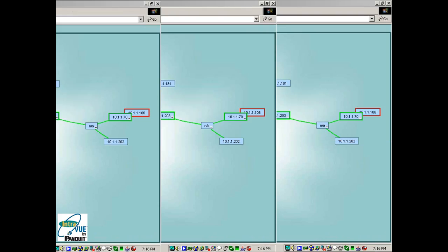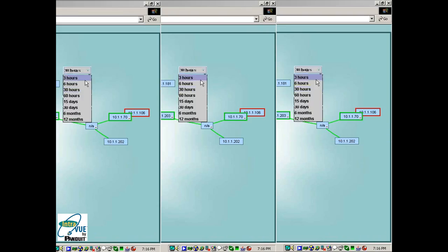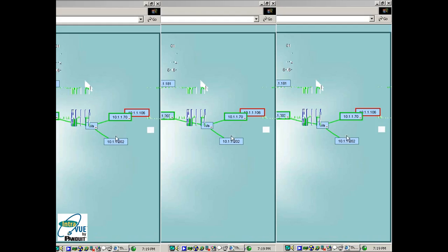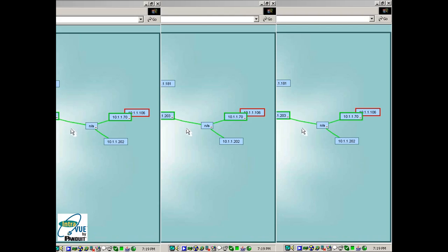Let's switch to the 3-hour view. We immediately see a correlation between the communication failures and the transmission of data from the device, indicating this is a communications problem. If we saw there were no lapses in the communications graphs at the bottom, yet there were lapses in the bandwidth data at the top, it would indicate an application issue in the device.